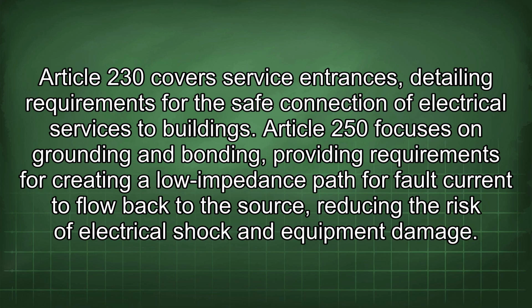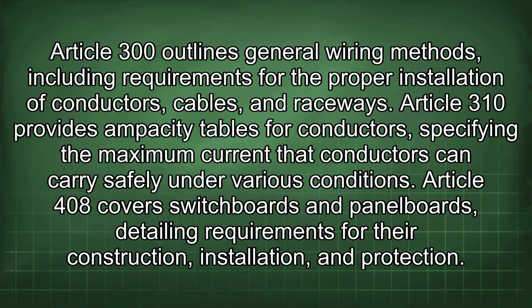Article 250 focuses on grounding and bonding, providing requirements for creating a low impedance path for fault current to flow back to the source, reducing the risk of electrical shock and equipment damage. Article 300 outlines general wiring methods, including requirements for the proper installation of conductors, cables, and raceways. Article 310 provides ampacity tables for conductors, specifying the maximum current that conductors can carry safely under various conditions. Article 408 covers switchboards and panel boards, detailing requirements for their construction, installation, and protection.